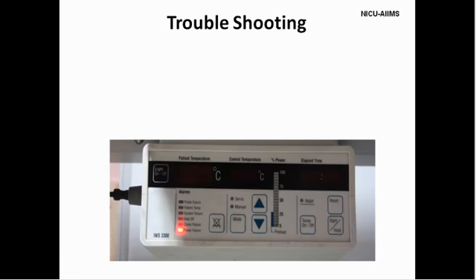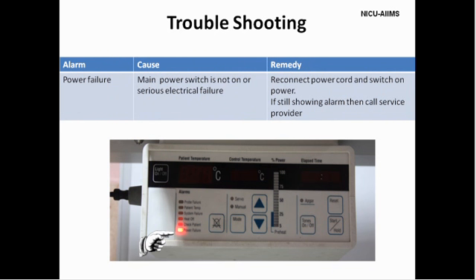Now, let us see some common problems faced while using the warmer and how do we tackle them. In case the main power switch is not on, then the warmer will give an alarm and indicate that there is power failure. If the alarm persists even after connecting the power cord and switching on the power, then the service provider may have to be called.